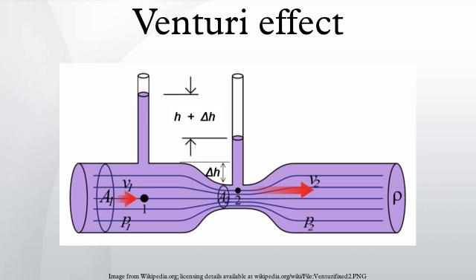A simple way to demonstrate the Venturi effect is to squeeze and release a flexible hose in which fluid is flowing; the partial vacuum produced in the constriction is sufficient to keep the hose collapsed. Venturi tubes are also used to measure the speed of a fluid by measuring pressure changes at different segments of the device. Placing a liquid in a U-shaped tube and connecting the ends of the tubes to both ends of a Venturi is all that is needed. When the fluid flows through the Venturi, the pressure in the two ends of the tube will differ, forcing the liquid to the low-pressure side. The amount of that move can be calibrated to the speed of the fluid flow.